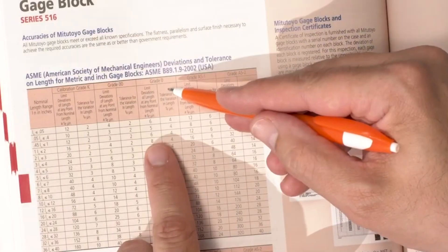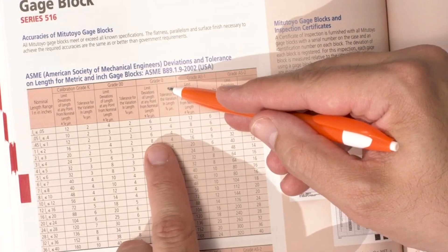Gauge Block grades are defined in national and international standards. In the U.S., we use the American National Standard for Gauge Blocks, ASME B89.1.9. You can also find the tolerance table in the Mitutoyo catalog. All manufacturers of Gauge Blocks sell them in grades in accordance to the standards.